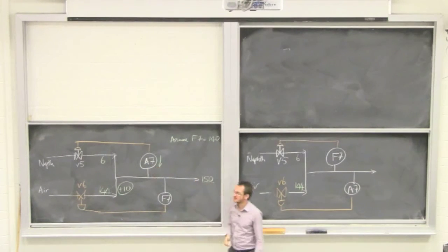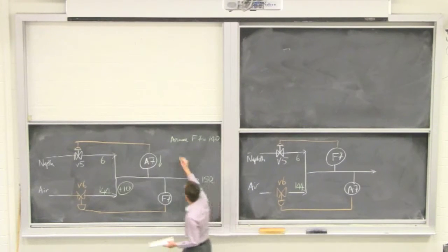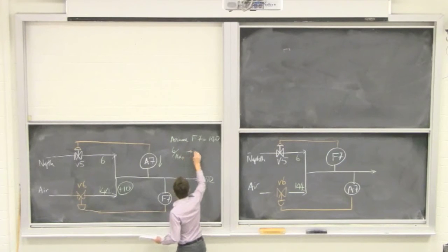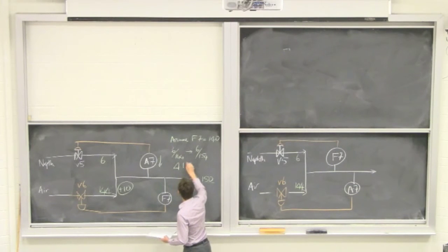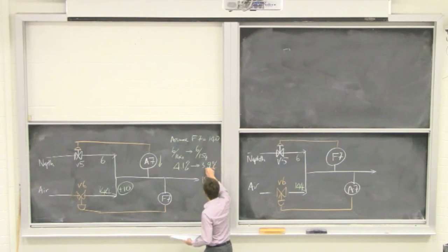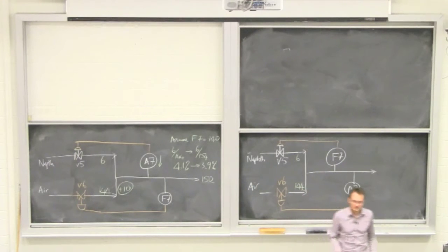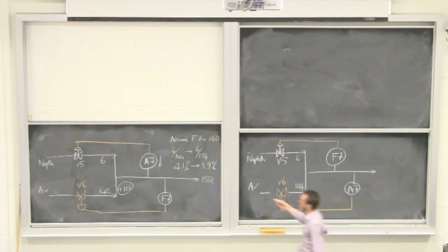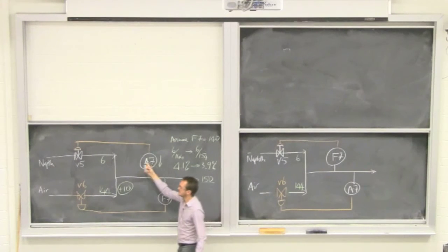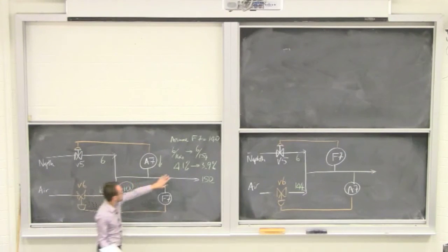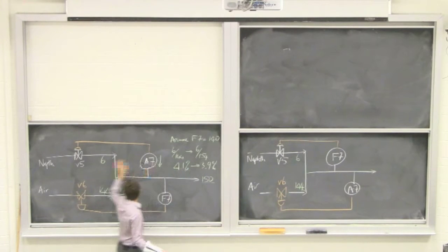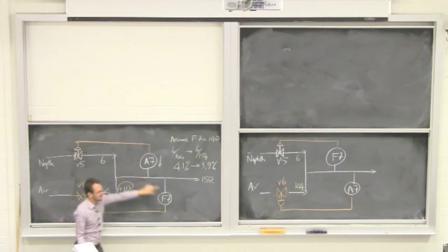But if we look at what's happened, the change in A7 has gone from 6 over 144 to 6 over 154. It's a change from 4.1% to 3.9% by weight. Okay? So you've affected that A7, but by very little. And what you'll start to see is that this control loop for A7 will try to counteract that effect and open naphtha. It will open naphtha because it wants to be at 4.1, it's gone down, so it will open this valve, which will then affect flow.